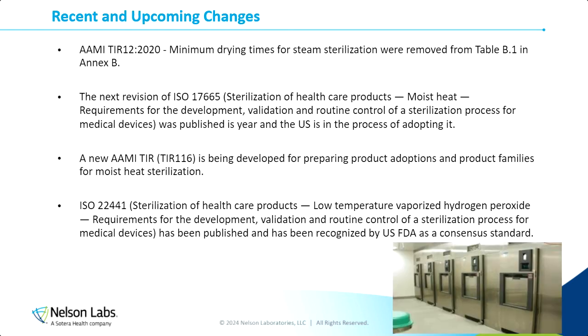So the major update that we've seen recently is again stemming from AAMI TIR12, which was updated in 2020, which states that minimum drying times for steam sterilization were removed from table B1 in Annex B, meaning there's just no recommendation for what your minimum drying time should be. We typically see 20 minutes being the common starting point during a dry time validation.